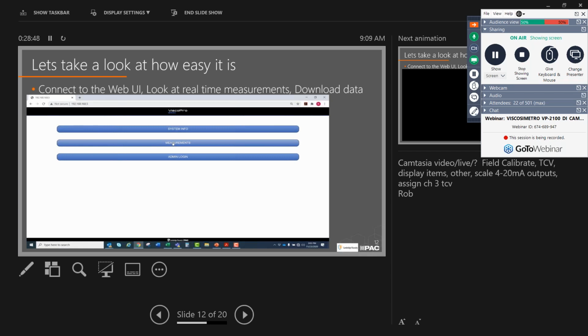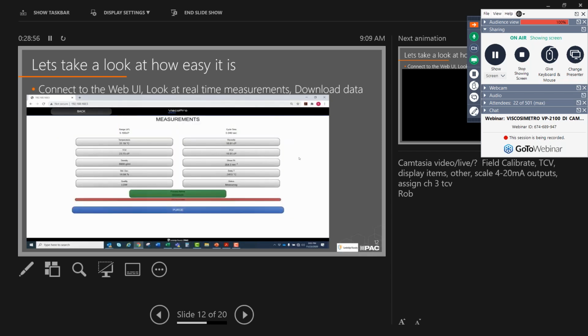So as you enter the web UI, now we're connected to the ViscoPro 2100, as a standard user, so you're limited on what you can access. But one of the things that you can do is you can take a look at the live measurements. So the live measurements will display the items such as viscosity, temperature, and other items that you have enabled, such as density or temperature compensated viscosity. It'll tell you the standard deviation of the reading, and it will also tell you the shear rate that the reading was taken at. So as a standard user, you can go in there and see these measurements live.